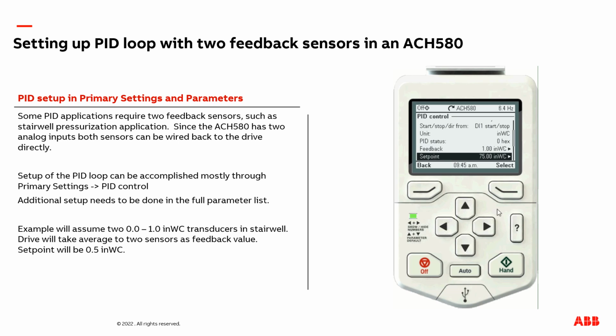Now I need to adjust my set point. The set point in our example is going to be a 1/2 inch of water column. So we're doing a constant set point also, which is just a fixed setting programmed into the drive parameter. So I'm going to adjust the 75 here to 0.5 inches of water column.